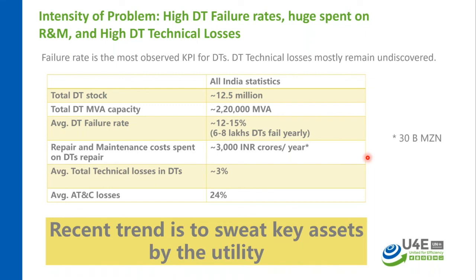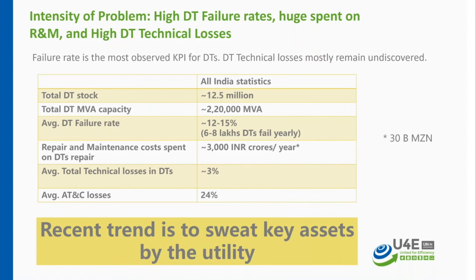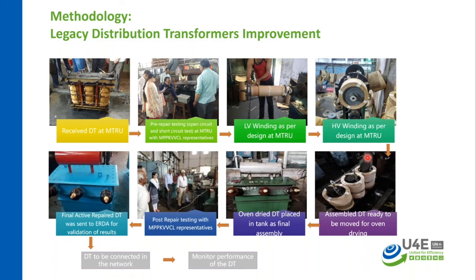As a result, we have created the intervention, and the utility has adopted revised practices of rewinding and repair, where KPIs have been set for performance improvement, for example, improving the kVA capacity, reducing the losses or improving the reliability. So the business change is that the utility has started doing a detailed inspection of the transformers which come for repair, and then takes the decision accordingly. The repair unit follows the same processes after the initial inspection and testing, wherein both load loss and the calibration of the temperature rise will be done through software.